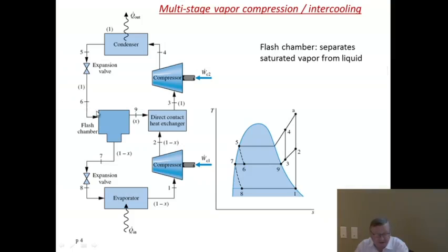So you have something here that's a mixed inside the vapor dome at point number 6. This has a certain quality, a mixture of vapor and liquid. And then you let gravity condense your liquid to the bottom, and gravity make the vapor go to the top, and you recycle the vapor here, and you take the liquid out to a second stage. This, of course, only works if you hold that thing vertical. If you put it on its side, or if you turn it upside down, it doesn't work.